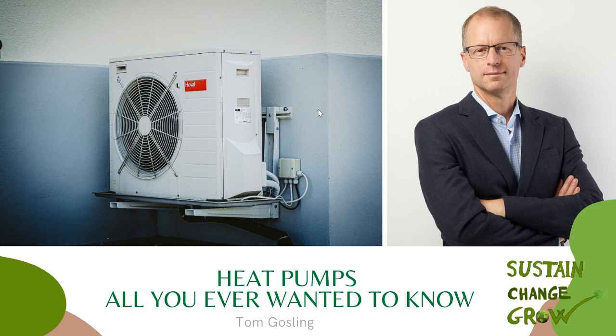However, the problem with heat pumps is that you have to have them well installed, because a unit of electrical power costs about 3 times as much as a unit of gas power. The efficiency of your heat pump needs to be generating at least 3 units of heat energy for every unit of electric energy. If it isn't, then you do run the risk of high bills. So one of the challenges is that they need to be installed to high quality in a way that enables them to operate efficiently. But that is perfectly possible, even in homes that are not terribly well insulated and even in cold weather.